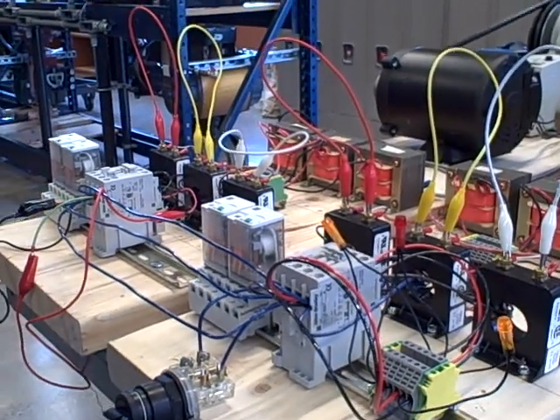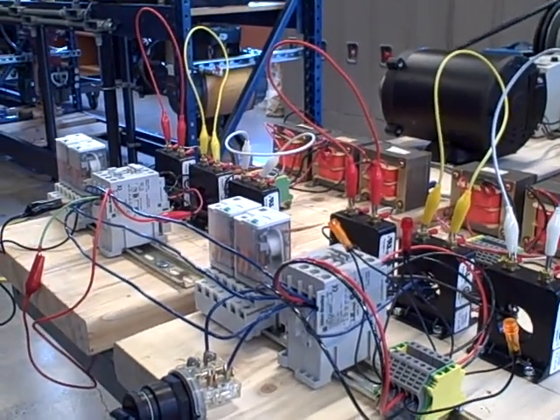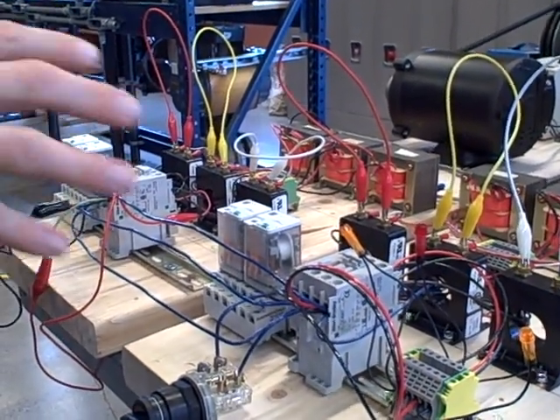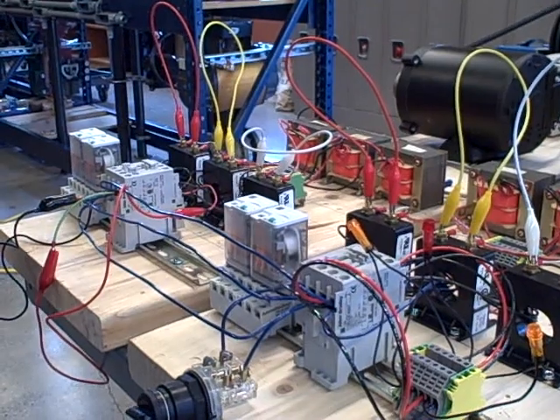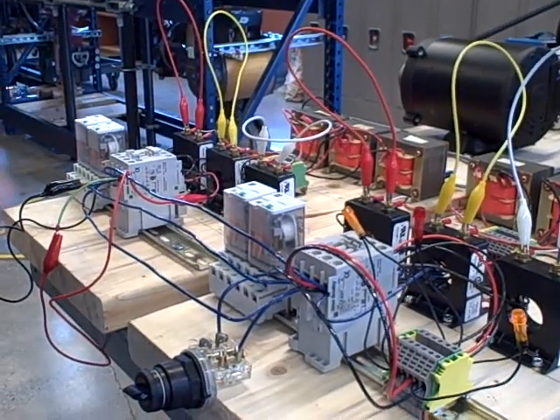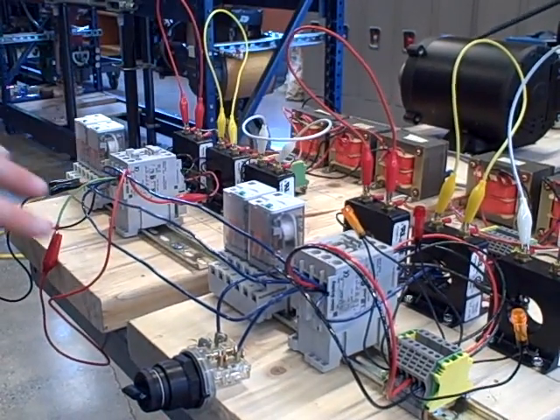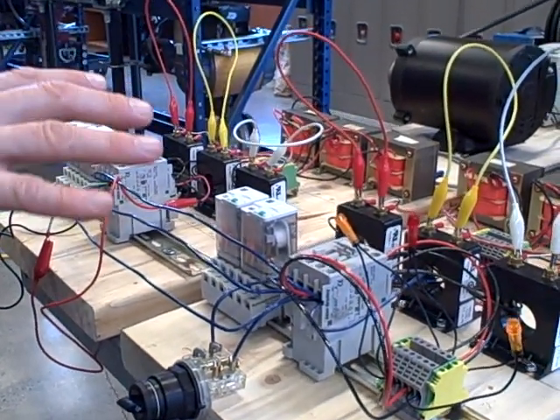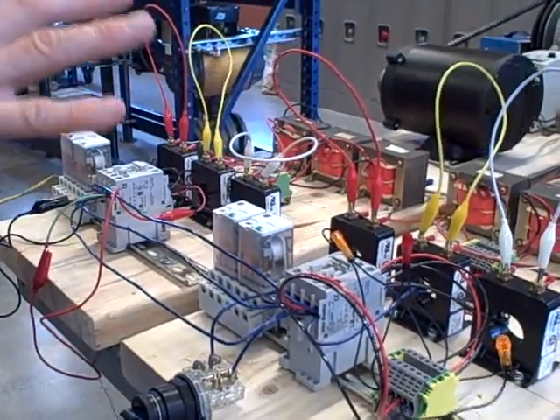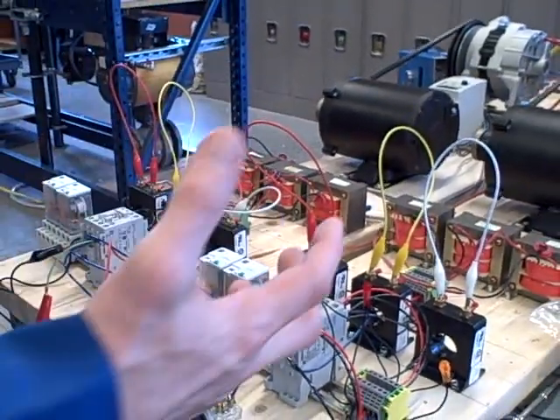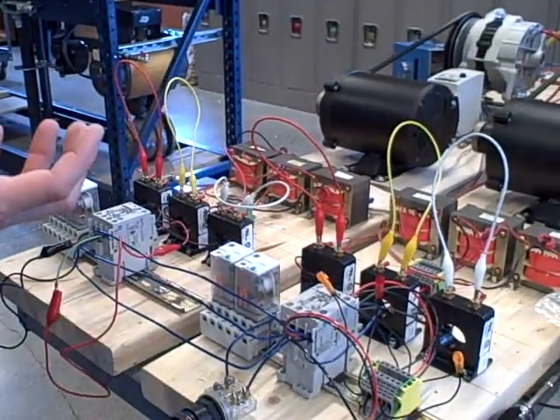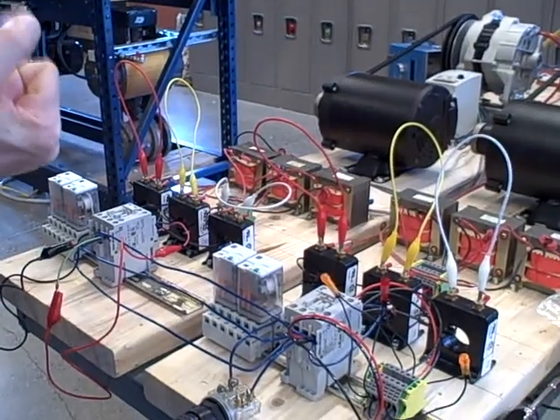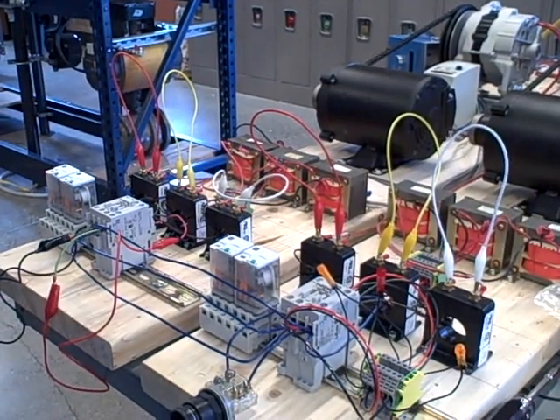And now they're parallel with each other. What's happening now when the generators are parallel, when they're on the same grid, is they are now electrically coupled with each other. And if one tries to spin faster or slower than the other, the other tries to pull it either up or down to speed, and they tend to stay in sync. It's almost as though we have a mechanical coupling, kind of a loose mechanical coupling between the generators being on the same grid.